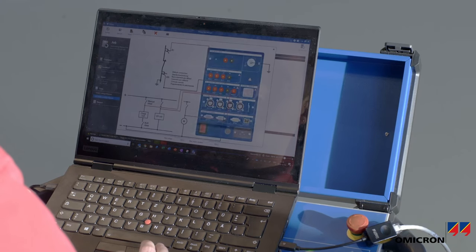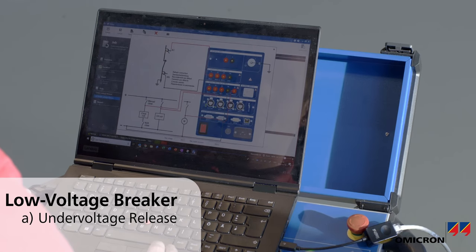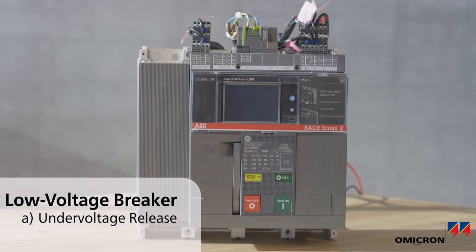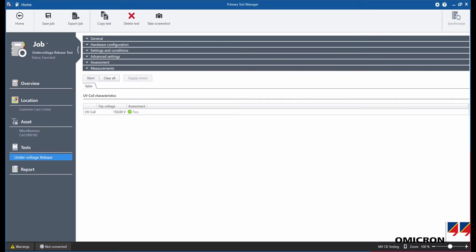CIBANO 500 can also test under-voltage coils. It first supplies the under-voltage release and closes the breaker, then the voltage is decreased until the under-voltage coil opens the breaker. After the test, we know the minimum voltage necessary for supplying the under-voltage release. In our case, the under-voltage release has tripped the breaker at 150 volts.